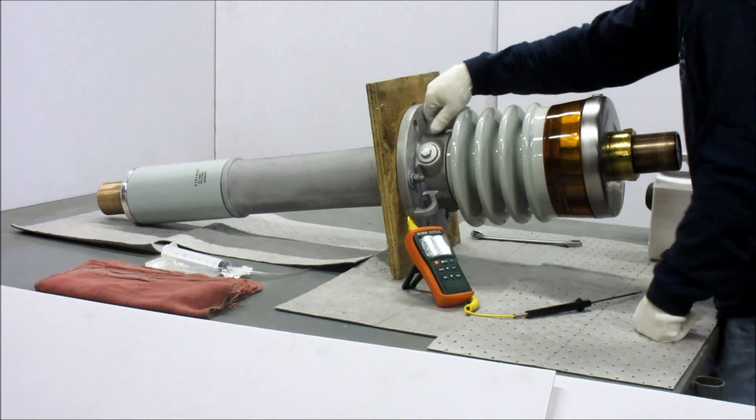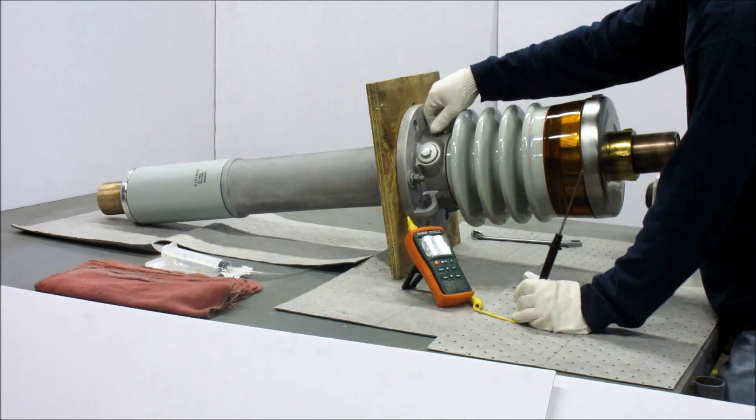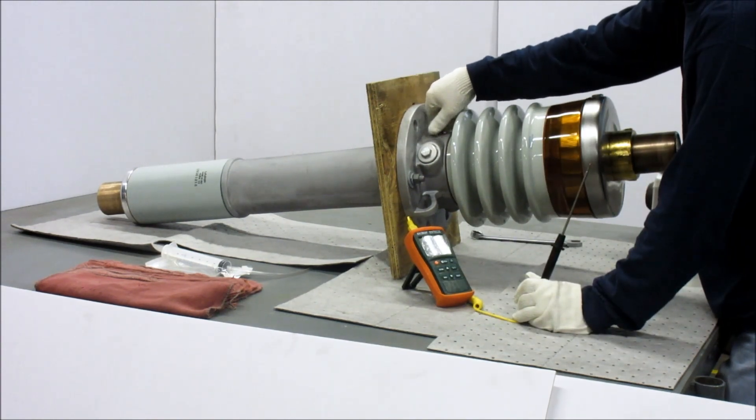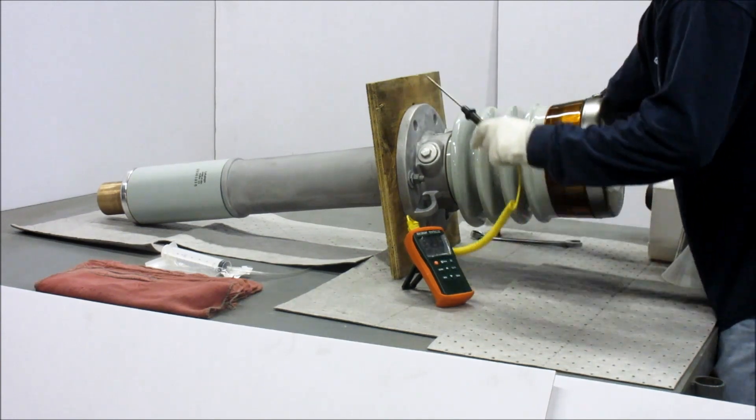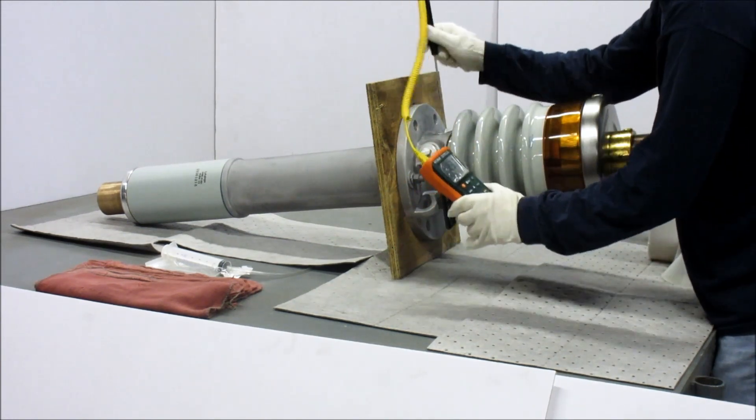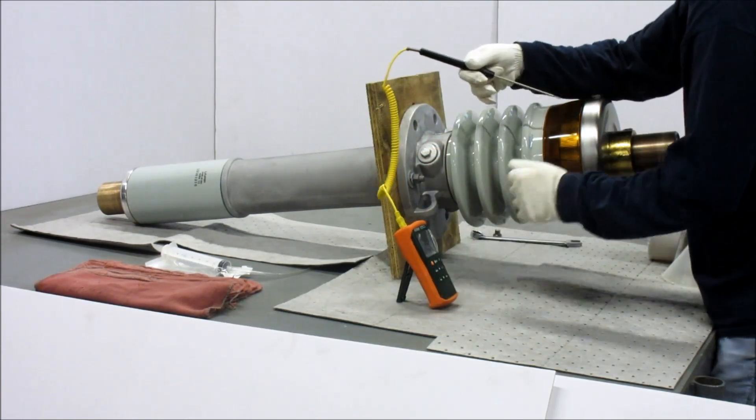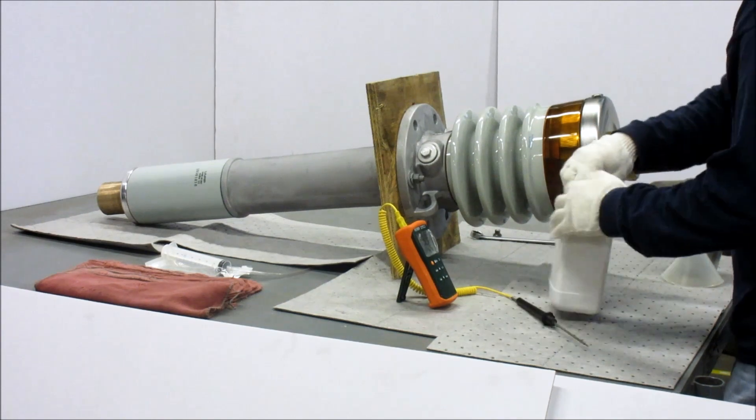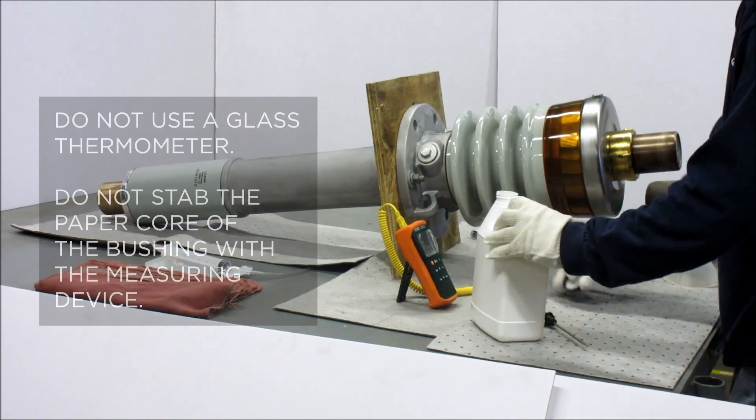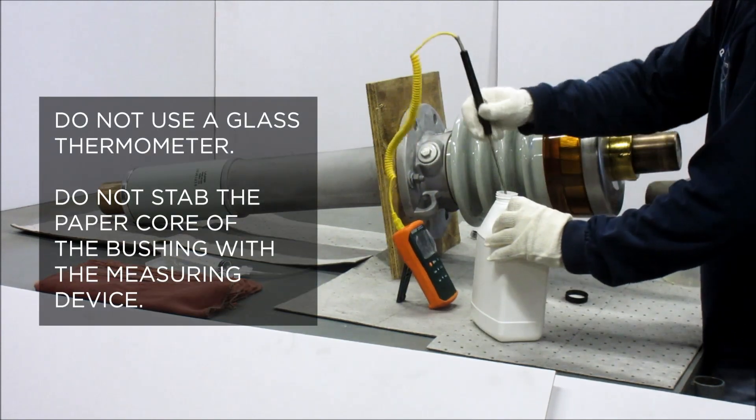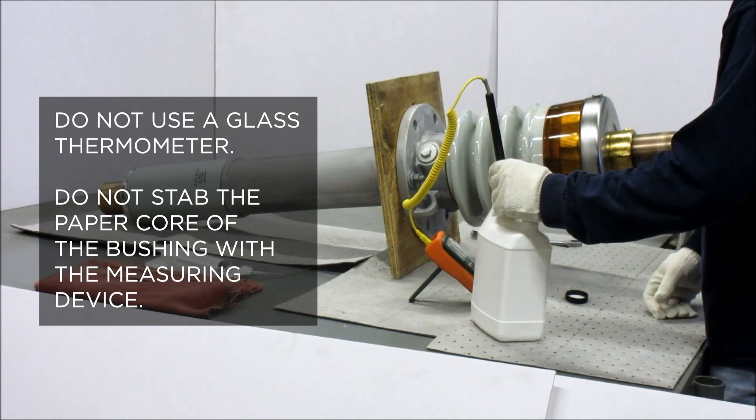Remove the oil fill plug from the flange and determine the temperature of the oil in the bushing and the oil that will be added. The best method is a dial thermometer or thermocouple inserted into the bushing oil. Ensure the oil to be added is the same temperature as the bushing's oil. Do not use a glass thermometer. Do not stab the paper core of the bushing with the measuring device.